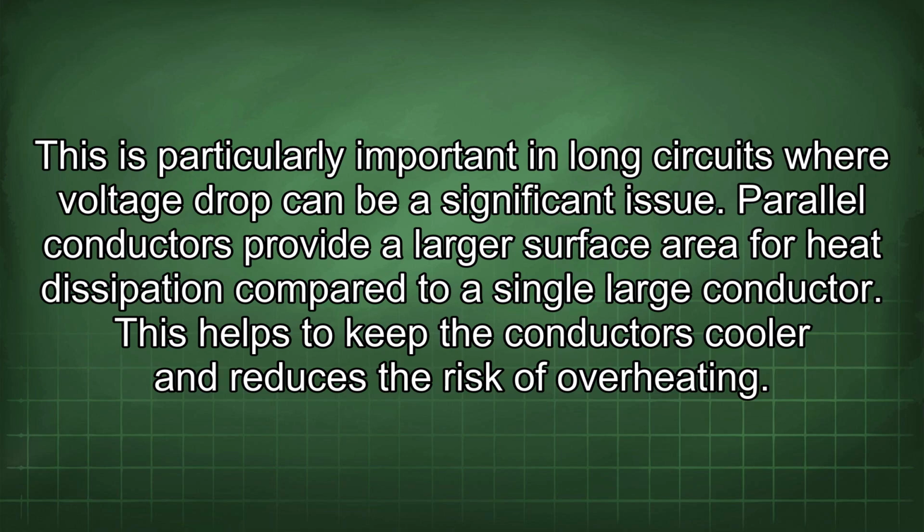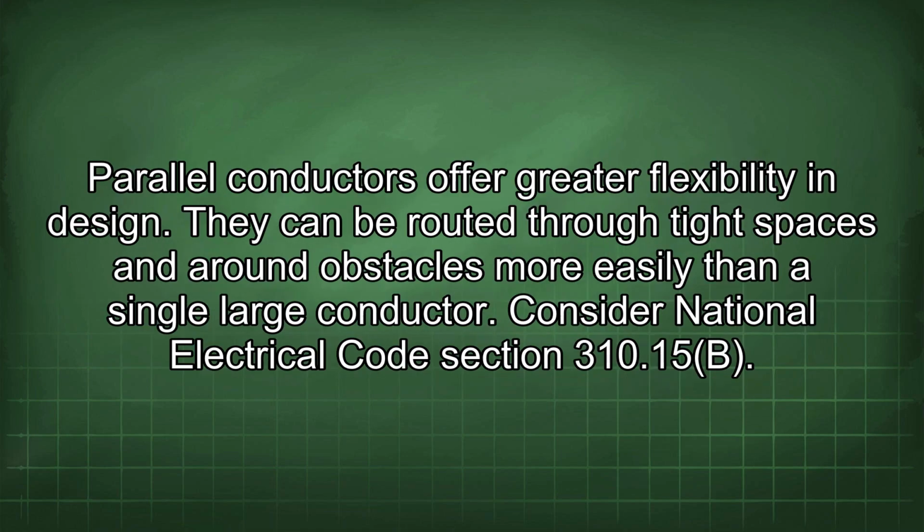Parallel conductors provide a larger surface area for heat dissipation compared to a single large conductor. This helps to keep the conductors cooler and reduces the risk of overheating. Parallel conductors offer greater flexibility in design. They can be routed through tight spaces and around obstacles more easily than a single large conductor.